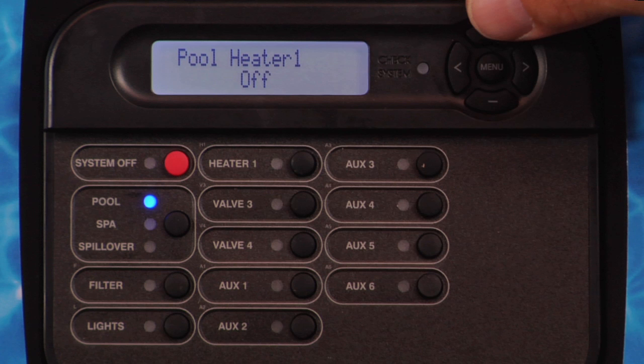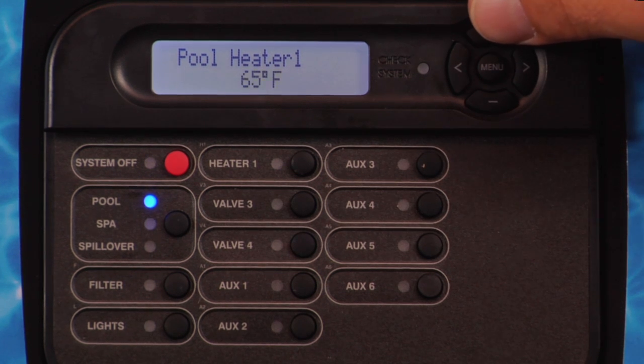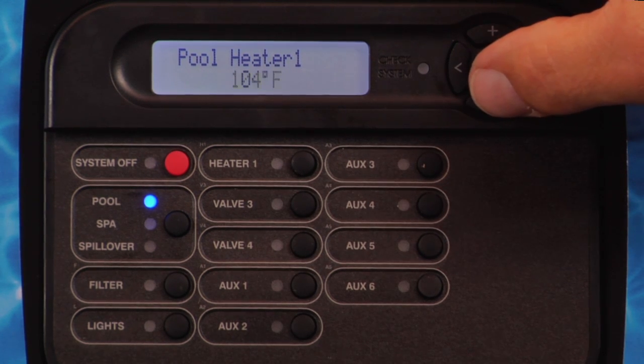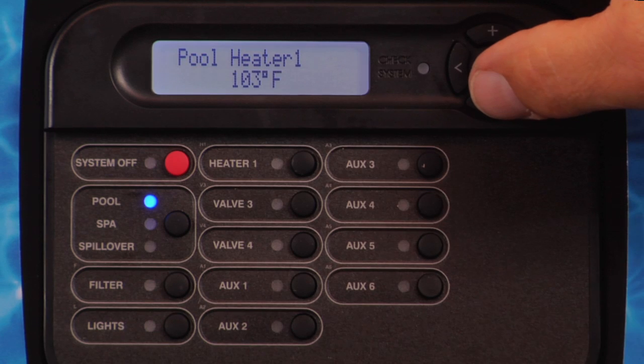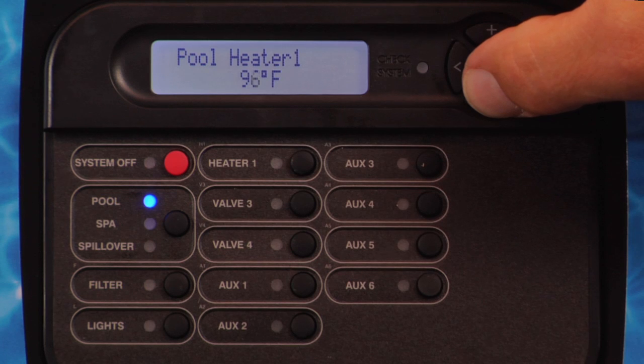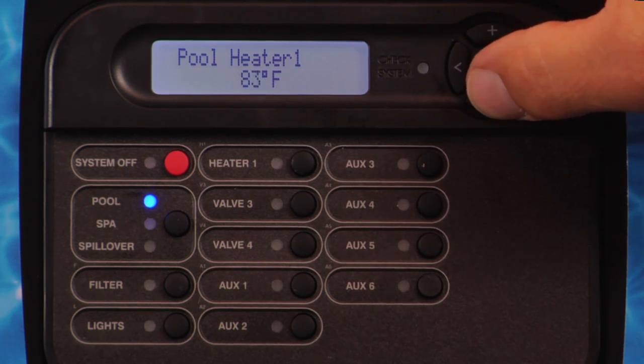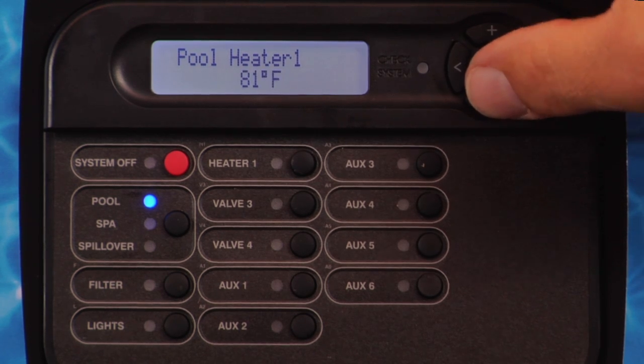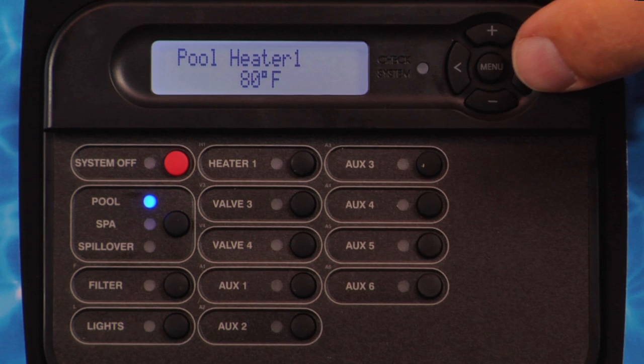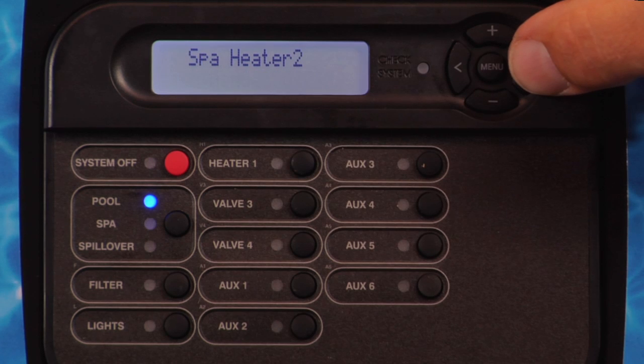If Heater 1 is enabled and the ProLogic is configured for Pool only or Pool and Spa, Pool Heater 1 will be displayed. Pressing the plus button will adjust the temperature from off to 65 degrees Fahrenheit through 104 degrees Fahrenheit and then wrap around. Pressing the minus button will adjust the temperature from off to 104 degrees Fahrenheit and then wrap around. Press the right arrow button.